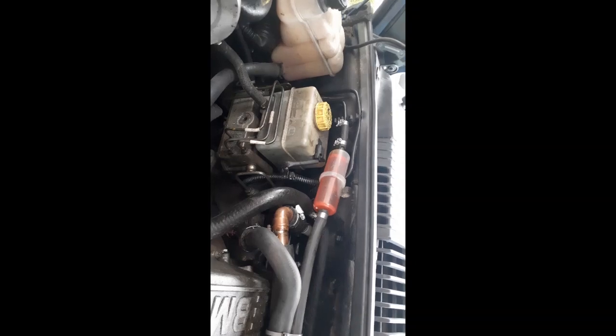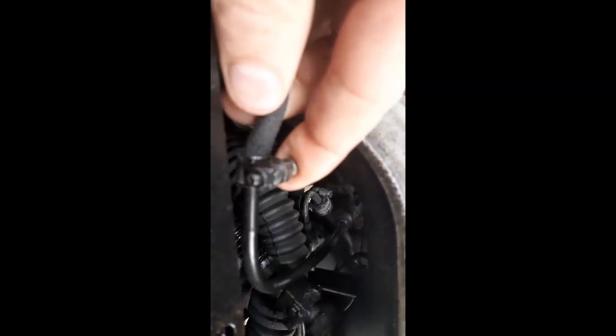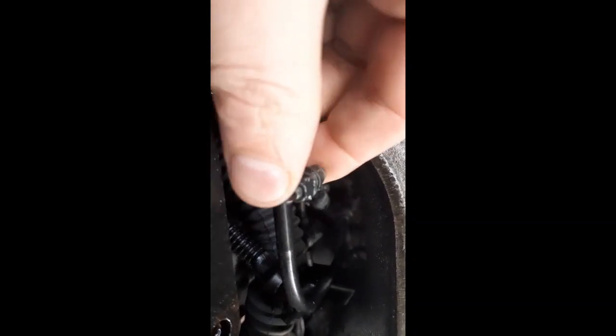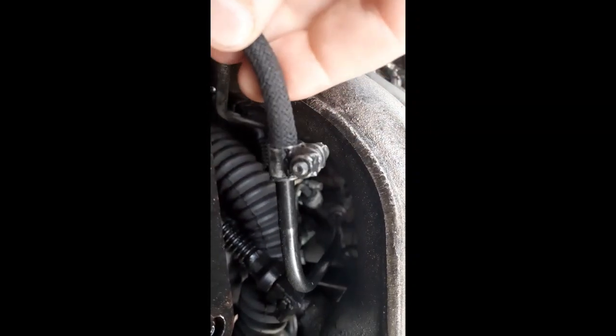Another thing is it takes loading off of that filter up there - it's only got as much fuel coming through it as the engine uses. Normally on a full return system, it's got the amount of fuel used plus the return volume, which is quite a lot, and that can put a lot of load on filters not designed to flow veg oil. These leak-off pipes go down a pipe and back down the return line into the tank, so the only thing returning back to the tank is the leak-off pipe flow.